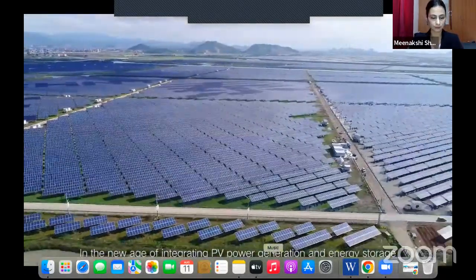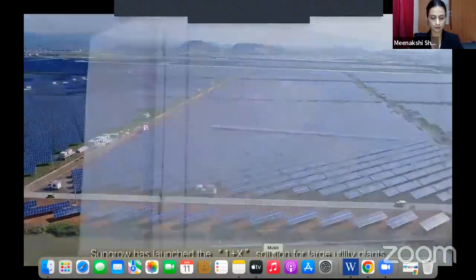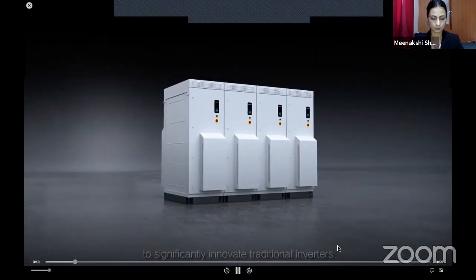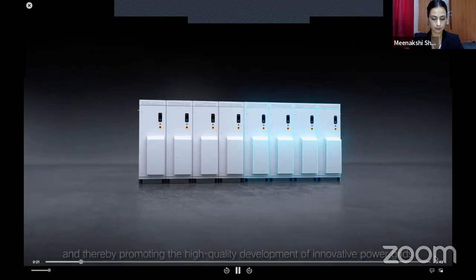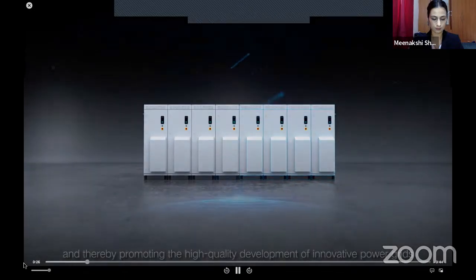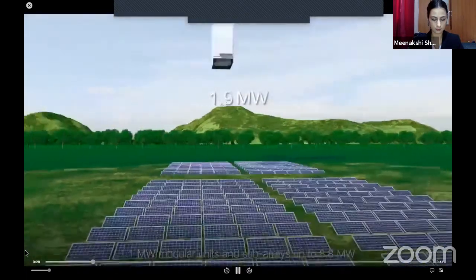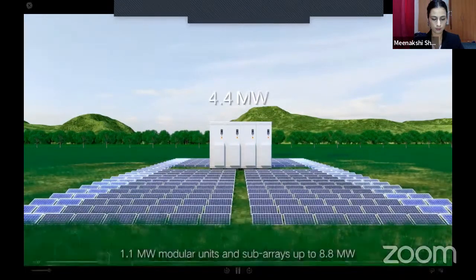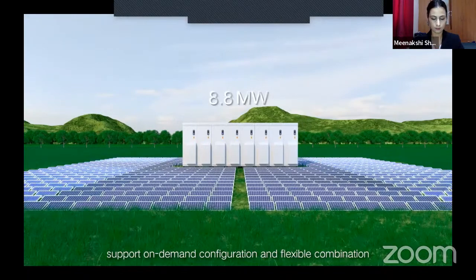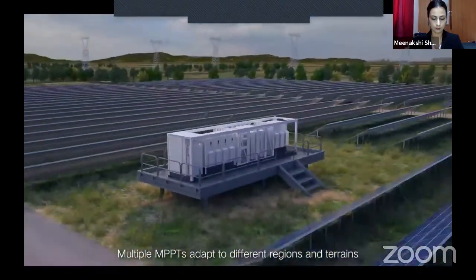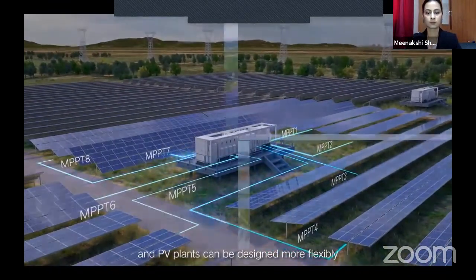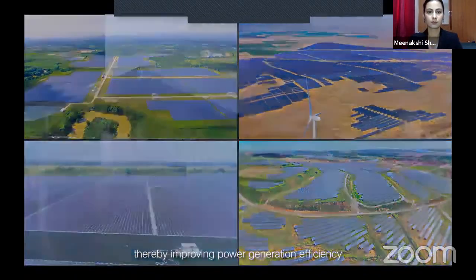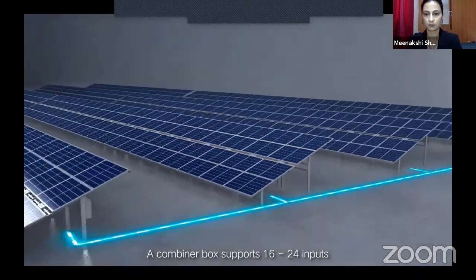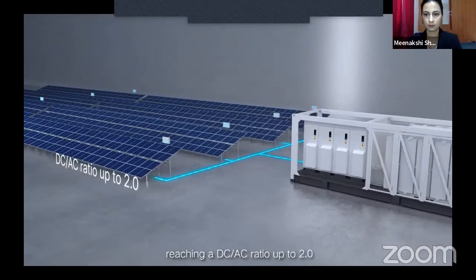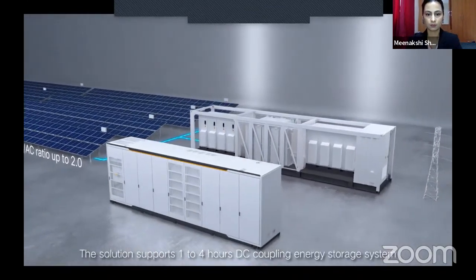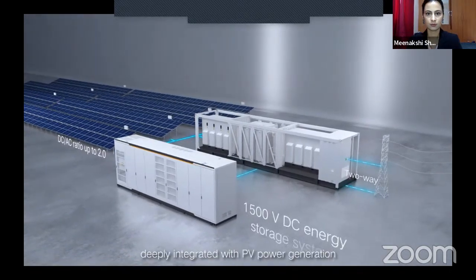In the new age of integrating PV power generation and energy storage, Sungrow has launched a 1+X solution for large utility plants to significantly innovate traditional inverters and thereby promote high-quality development of innovative power grids. 1.1 megawatt modular units can be combined up to 8.8 megawatts, supporting on-demand configuration and flexible combination. Multiple MPPTs adapt to different regions and terrains, and PV plants can be designed more flexibly, thereby improving power generation efficiency. A combiner box supports 16 to 24 inputs, reaching a DC-AC ratio of up to 2.0. The solution supports 1 to 4 hours DC coupling energy storage system, deeply integrated with PV power generation.